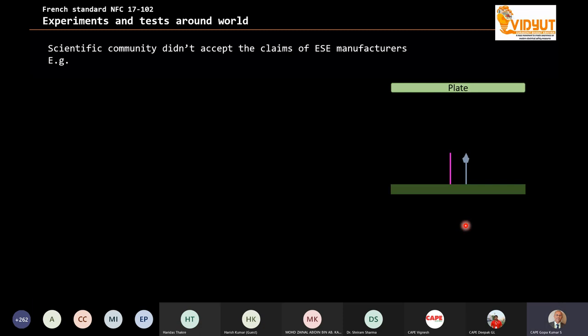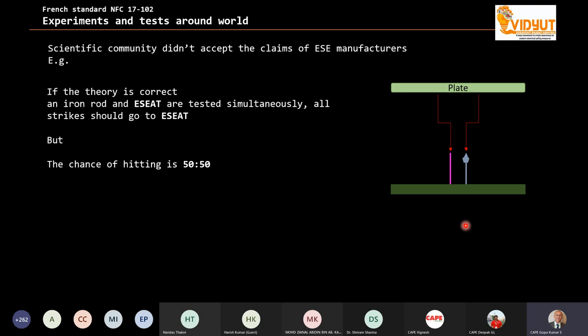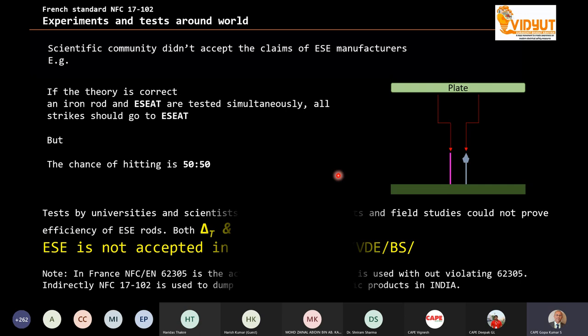So what scientists did, they connected an iron rod and an ESE rod. And if the claim of the ESE vendors is correct, if the ESE is more efficient, and you put 100 strikes, all 100 strikes should go to the ESE rod. So they made the charge, they did the testing, and finally the result is, if the theory is correct, when the iron rod and ESE are tested simultaneously, all strikes should go to the early streamer emission air termination. But it is not so. It's about 50-50. In some cases, ESE will have 60, the normal rod will have 40. In another case, sometimes the normal rod has 70 and the ESE has 30. So the claim of the ESE rod companies is absolutely wrong. This is one of the ways it is proven.